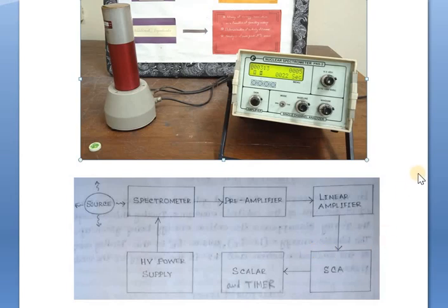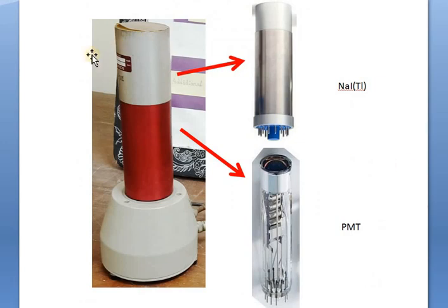Now, okay, so this is basically the detector, how it looks like. Inside this module that you are seeing right now, we actually have this sodium iodide scintillator detector, which looks like this, and this one is put inside this box along with the photocathode and the photomultiplier tube, which actually looks like this. I am showing you the real world pictures of the detector.